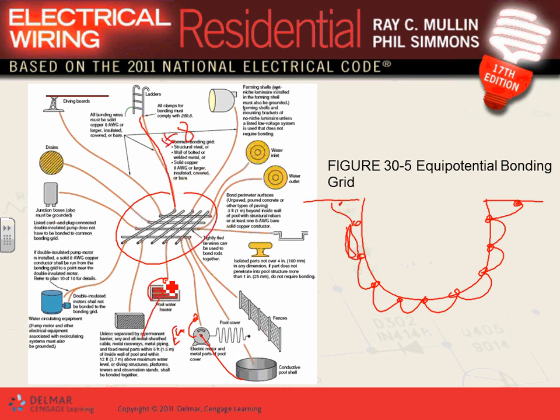Any comments, guys? Any questions? This is the detail that you guys are going to be picking and putting in your plan for the swimming pool. You use number 8 copper to tie all these together, minimum number 8 copper, and it must be solid too. It's not stranded. Solid number 8 copper. It can be covered, insulated, or bare to tie all these systems together.